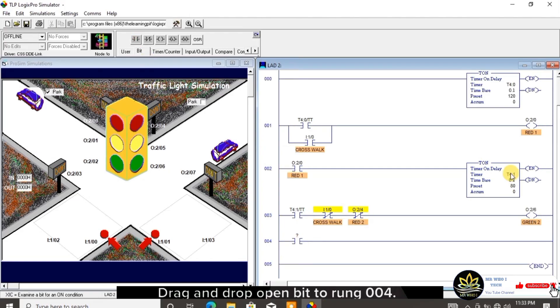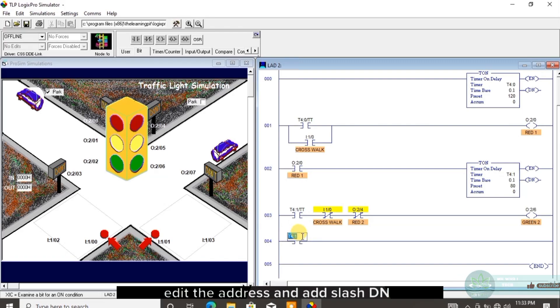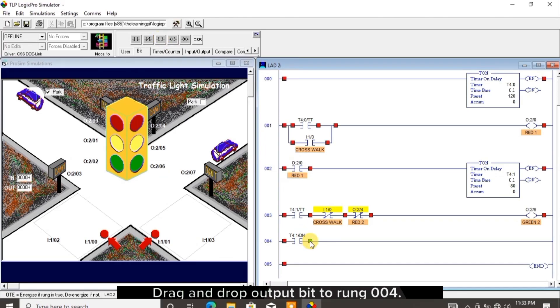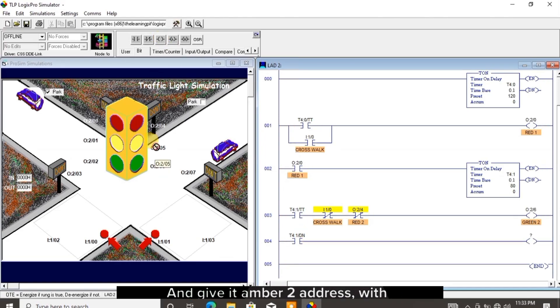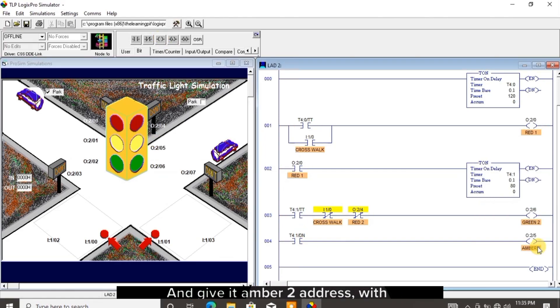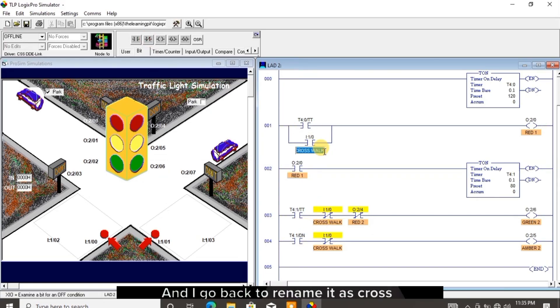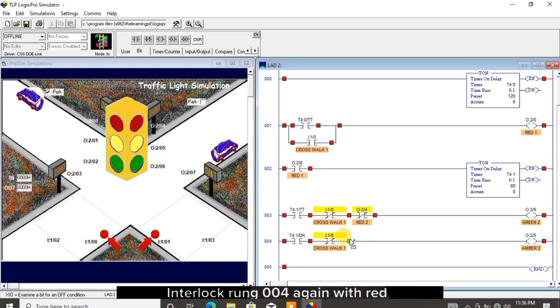Drag and drop open bit to rung 004 and drag and drop timer 1 address to it. Edit the address and add /DN to it. Drag and drop output bit to rung 004 and give it the amber 2 address with the name. I interlock rung 004 with the crosswalk and go back to rename it as crosswalk 1. Interlock rung 004 again with red 2.